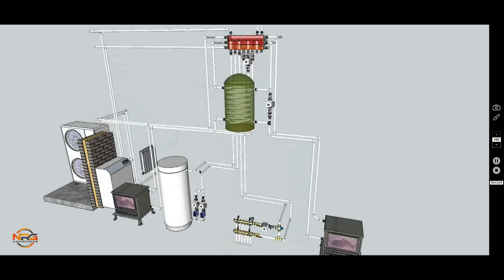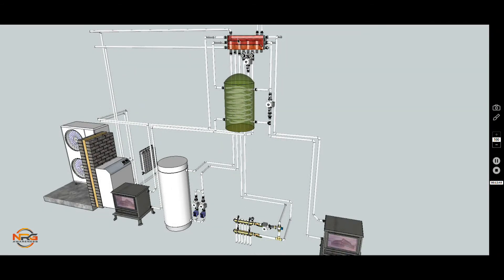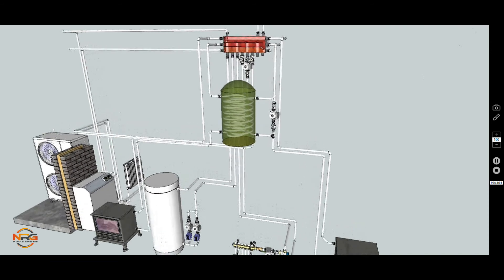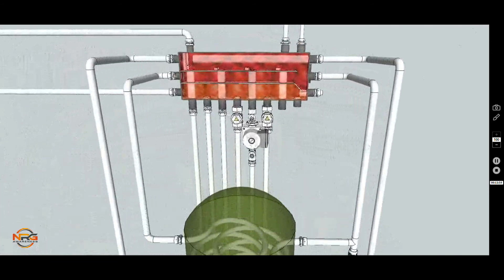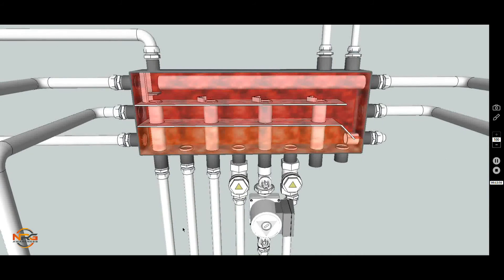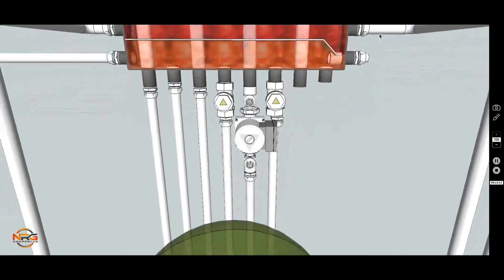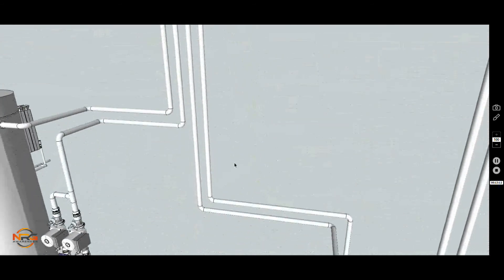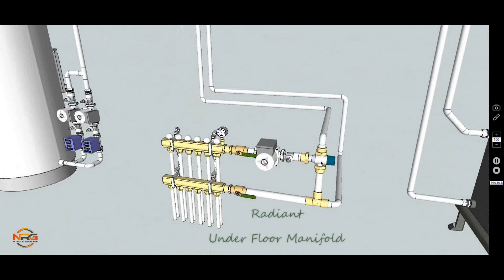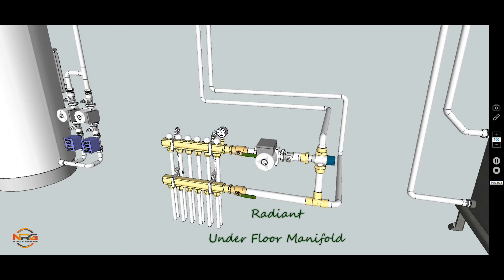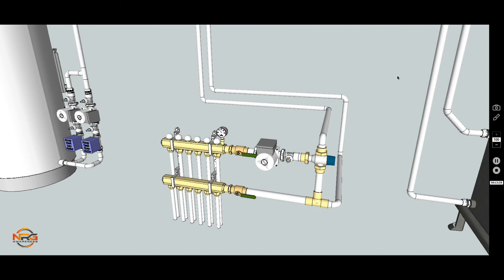If we now want to consider putting in an underfloor heating circuit, we would take our flow again from the hottest water, come down into the manifold. At this point in the manifold, the flow and return are only affected by the pump on the manifold, and there's no pump at the Energy Zone manifold. The reason is it doesn't need a pump here. If the mixing valve pump arrangement at the underfloor manifold needs heat, it will draw it down through the flow pipe, through the mixing valve and around. But if the pump is already satisfied with regard to the amount of heat energy in the system, it will simply take this path through the floor, back from the floor and around again. As the mixing valve opens, it will open this port and draw more heat down. In that fashion, the cold water will be put back up into the coldest chamber of the Energy Zone unit and be heated by whatever boiler is being called at that time.